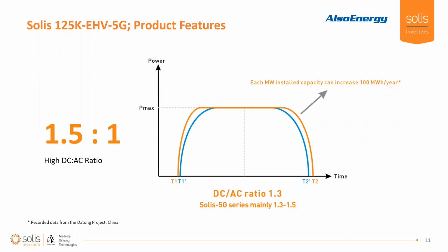So loading up the inverters, you get a lot of freedom here because you don't necessarily need to load it up all the way to the max voltage on every MPPT. You may want to do that on one particular inverter, but on the next inverter you may load that down with a lower voltage and still get peak efficiency out of both units.